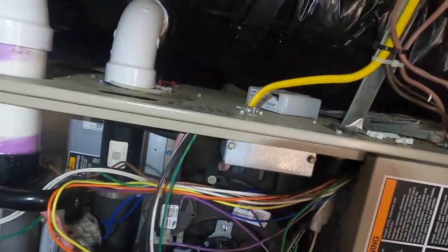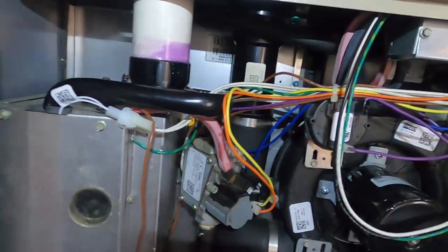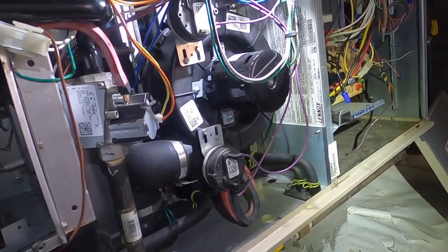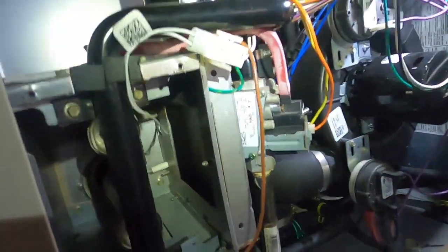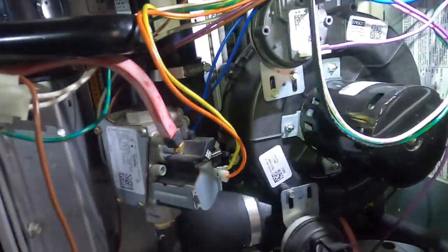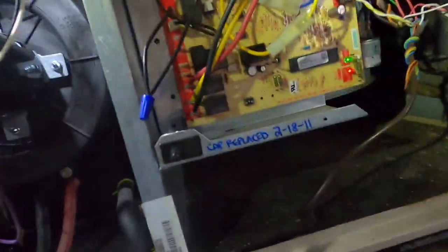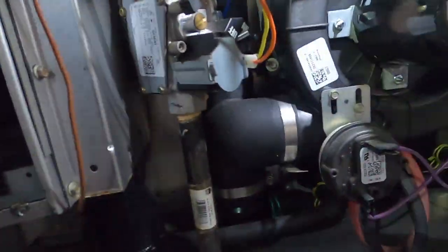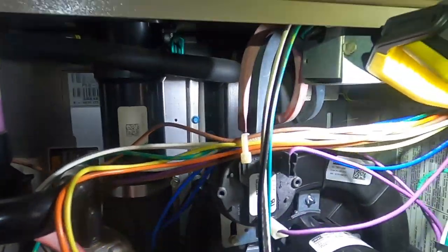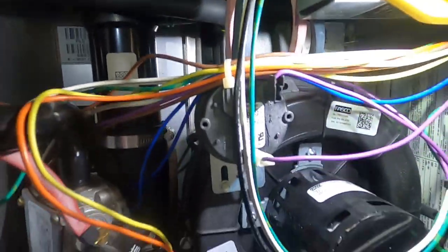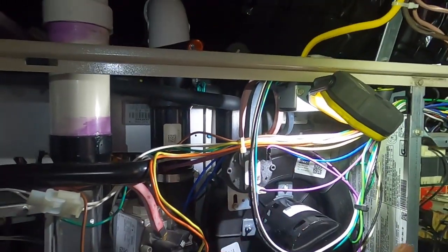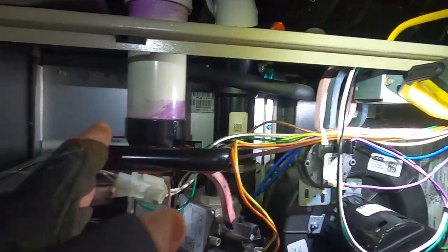So anytime somebody mentions a heat exchanger and I come out for a second opinion, I want to check it. So checking the heat exchanger, I'm probably going to have to pop these burners out, get in there with the camera, maybe do a pressure test on it. But it's a 90% furnace, so getting this blower out and being able to see the heat exchanger ain't going to happen. You're going to have your secondary coil for the heat exchanger right in there, in between the blower compartment and the actual heat exchanger itself.